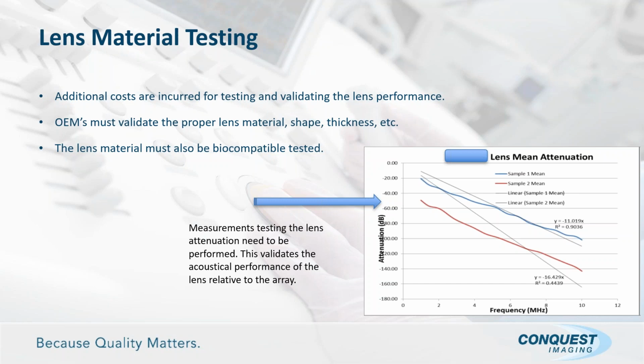Is it scattering? One of the things that we've seen over the last several years, certain probes of Philips, GE, Siemens, all three specifically do it. They've got lenses with various metals in them. We've seen gold, silver, aluminum, and all these things are done based on the arrays they're using on certain models, to improve the image performance, but also to make sure that they're focusing their beam properly, reducing noise, etc. So there's a lot of testing that goes into these lenses.